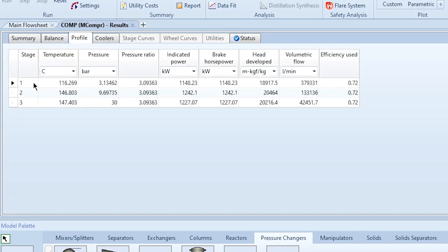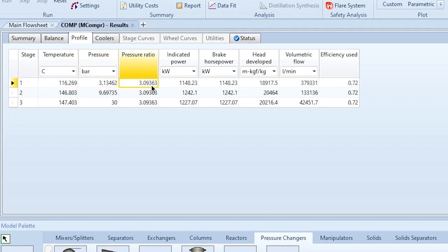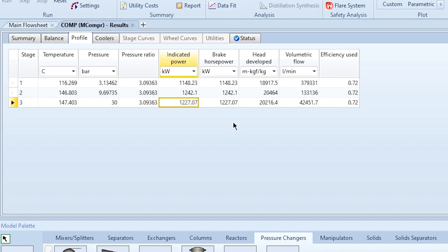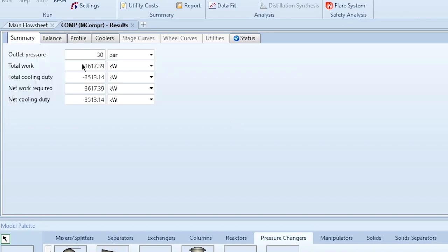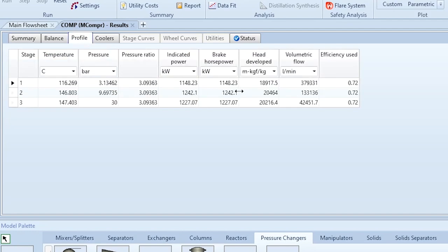In the Profile tab, after compression in stage one the temperature is 116.269°C and the pressure is 3.13462 bar, with a pressure ratio of 3.09363. This pressure ratio is constant across all three stages. Stage power values are 1148.23 kW, 1242.1 kW, and 1227.07 kW — summing to 3617.39 kW total compressor power.